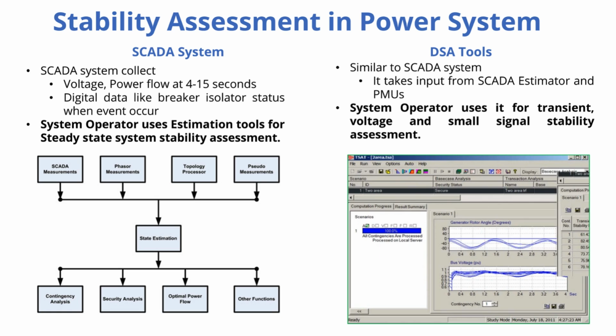What about DSA tools? DSA is Dynamic Security Assessment. These are more sophisticated. They take input from SCADA, maybe PMUs too, and use detailed system models to run simulations in near real time. What kind of simulations? They assess dynamic behavior. Operators use them to check the stability impact of potential what-ifs. What if this line trips? What if that generator fails? Would it cause transient instability, voltage problems, oscillations? It helps assess risk based on the current system state.